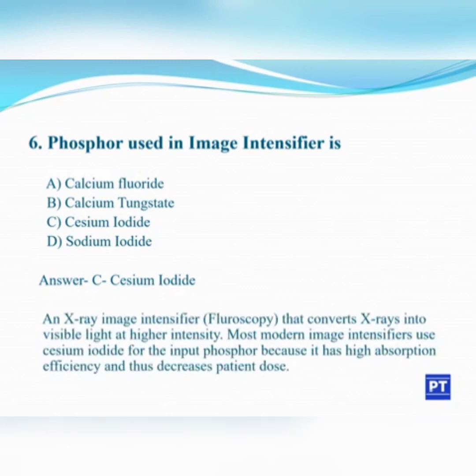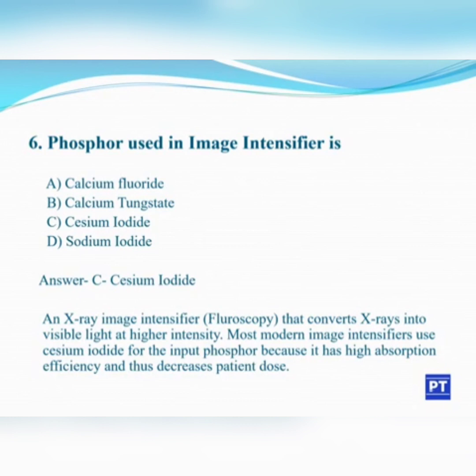An X-ray image intensifier, otherwise known as fluoroscopy, converts X-rays into visible light at higher intensity. The most modern image intensifiers use Cesium iodide for the input phosphor because it has high absorption efficiency and thus reduces the patient dose. The phosphor used in the image intensifier is therefore Cesium iodide.